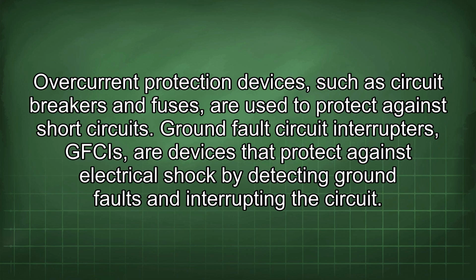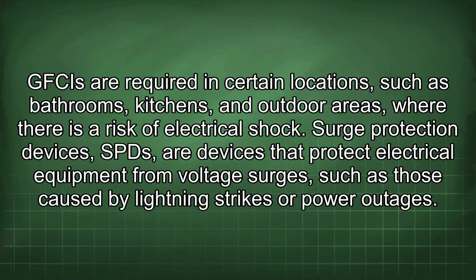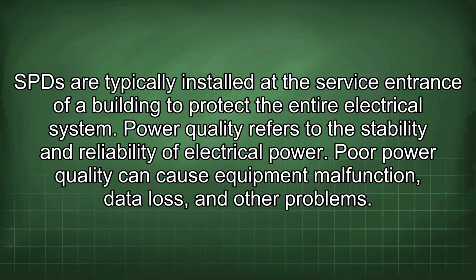Ground fault circuit interrupters, GFCIs, are devices that protect against electrical shock by detecting ground faults and interrupting the circuit. GFCIs are required in certain locations, such as bathrooms, kitchens, and outdoor areas, where there is a risk of electrical shock. Surge protection devices, SPDs, are devices that protect electrical equipment from voltage surges, such as those caused by lightning strikes or power outages. SPDs are typically installed at the service entrance of a building to protect the entire electrical system.